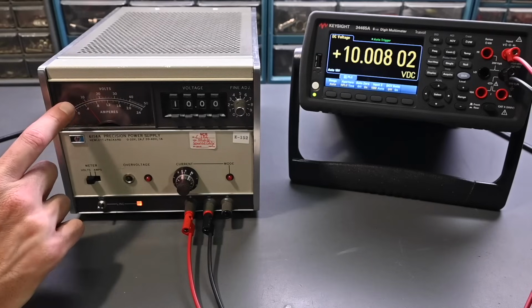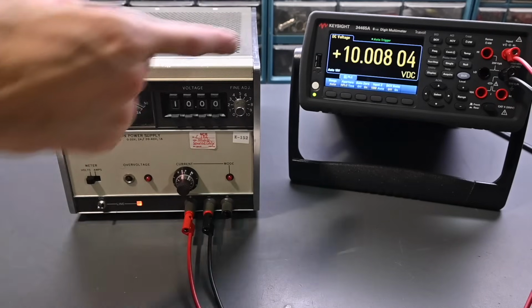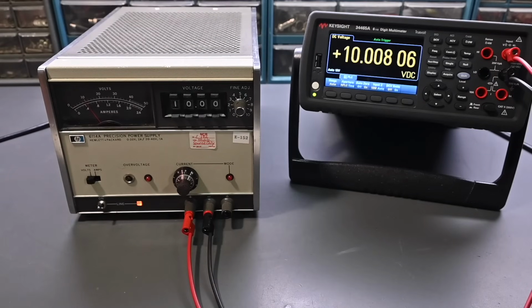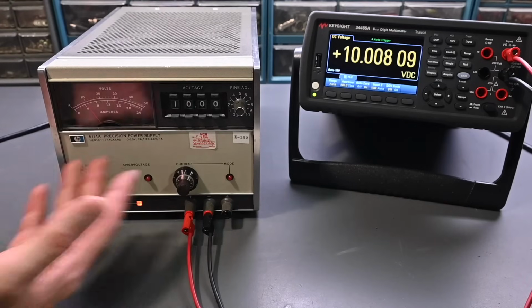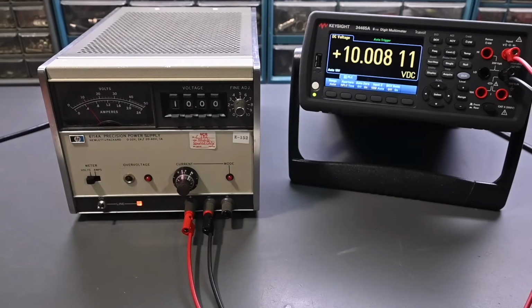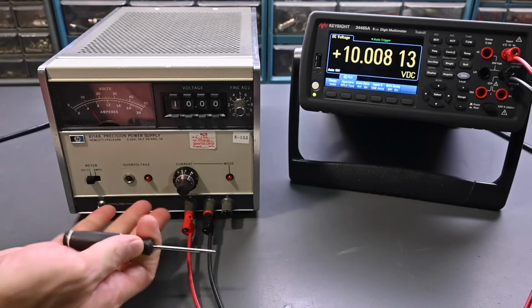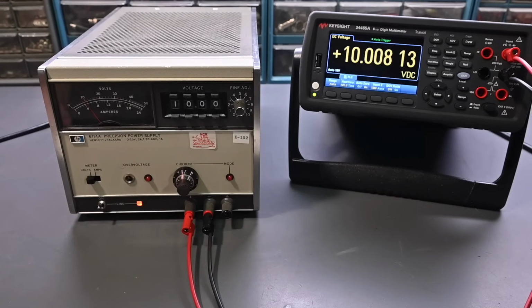But the indication right here, it's right at the 10 volt tick mark, and again, very, very close on that digital multimeter. And that Keysight digital multimeter is under a factory calibration. It's known to be very, very accurate. So right now it looks like everything's working okay. But sometimes when I turn this on, the fault happens right away. In this case, it did turn on the way that it was supposed to.